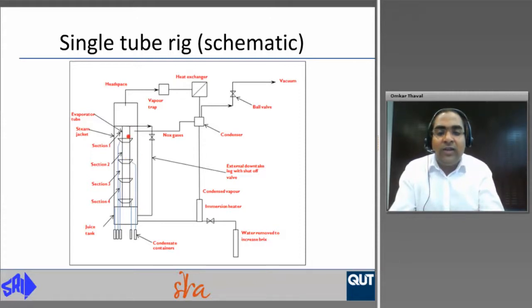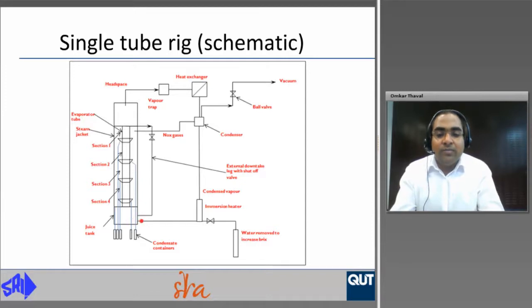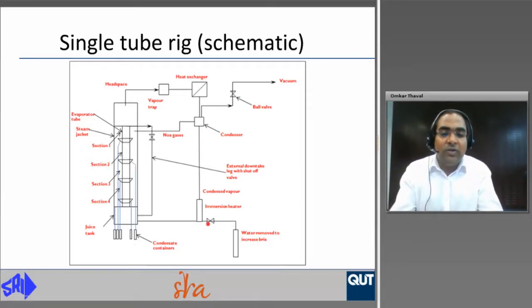A fifth condensate container collects condensate that condenses on the inner walls of the steam jacket, which plays no role in tube heat transfer. Juice boiling inside the tube produces vapours in the headspace, which are taken to a vapour trap to remove entrained juice, then into a heat exchanger where they are condensed and returned to the juice tank. Before being added back, the condensed vapour passes through an immersion heater to maintain the juice tank at boiling temperature. A connection was added to remove excess water to increase brix, and an external downtake leg with a shutoff valve acts as a downcomer during operation. A noncondensable gas line is connected to the vacuum.